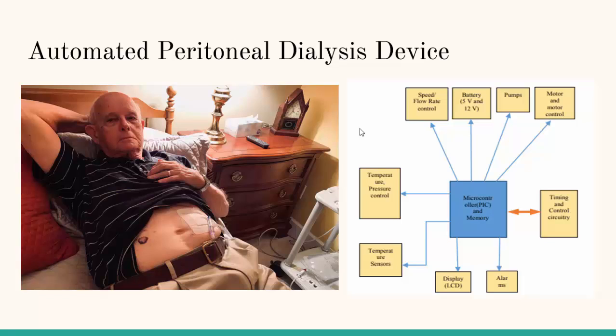The dialysis, which is filled in the peritoneal cavity of the patient, is to be heated at a temperature of 37 to 40 degrees. This is to be controlled accurately as per the body temperature of the patient. Flow rate control. The rate at which the fluid is filled in the cavity should be uniform. This is also controlled by a timing circuit. A timing circuit can also be used to control the flow of dialysate in the body.